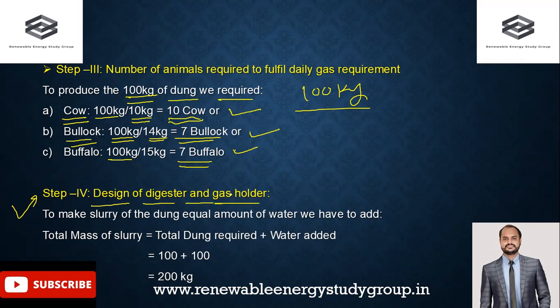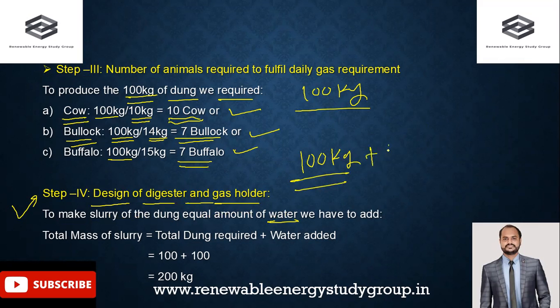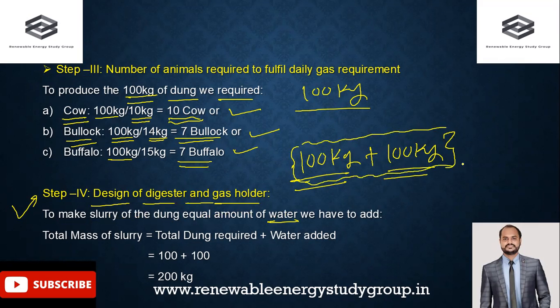Step 4 covers the design of the digester and gas holder system. The digester volume depends on the daily slurry input. To make slurry, equal amounts of water and dung are mixed — so 100 kg of dung plus 100 kg of water gives a total slurry mass of 200 kg per day.